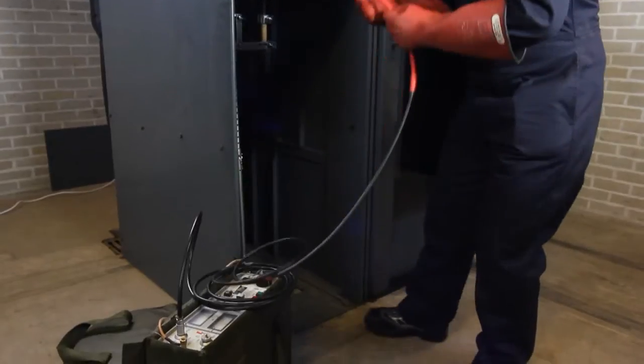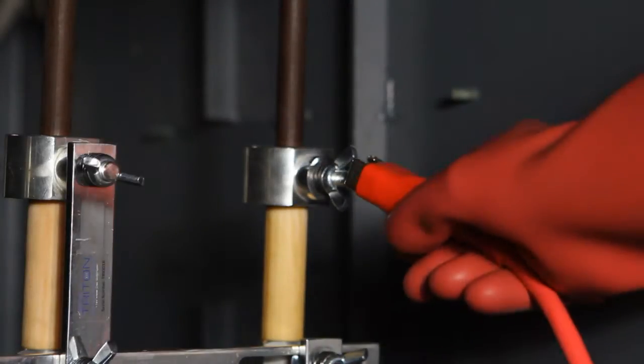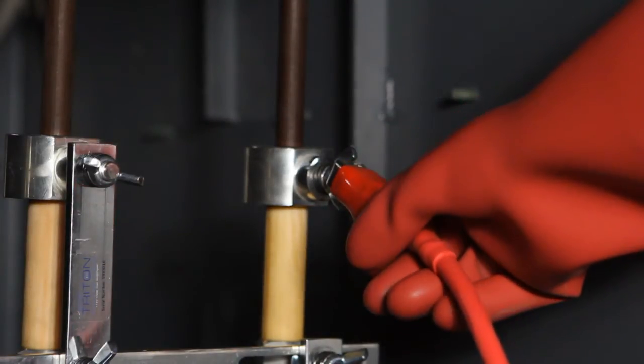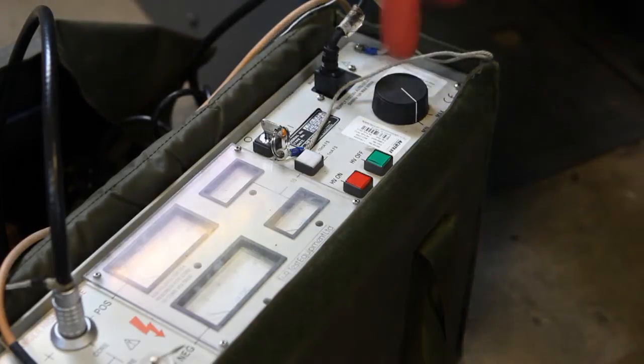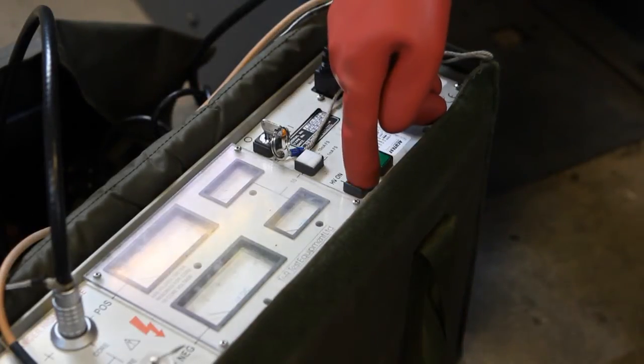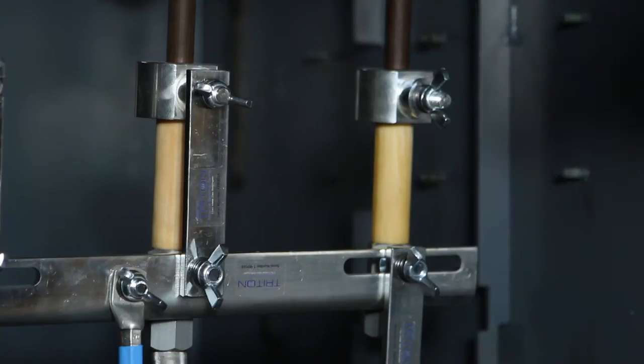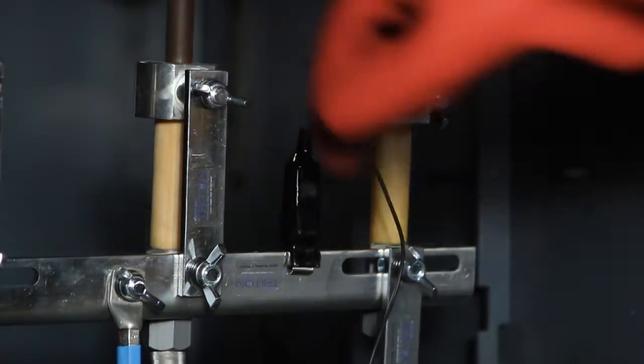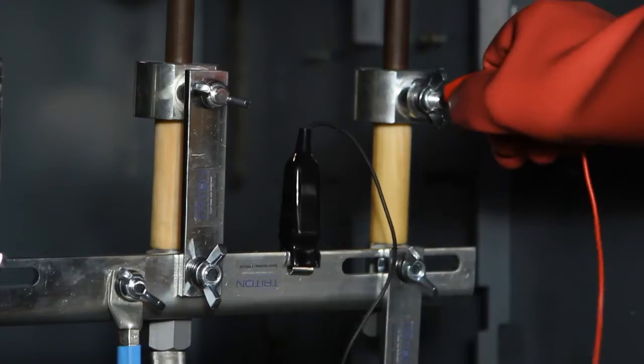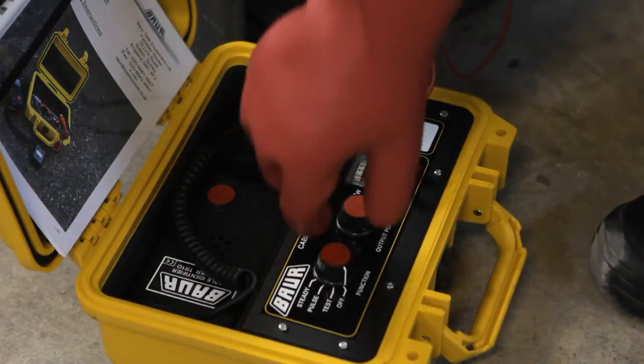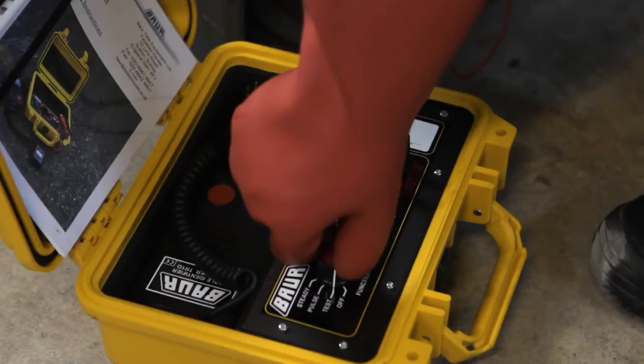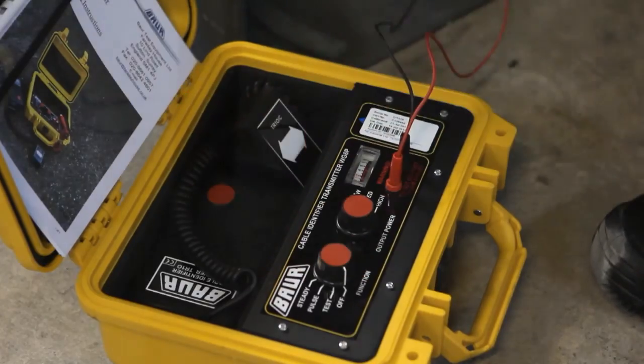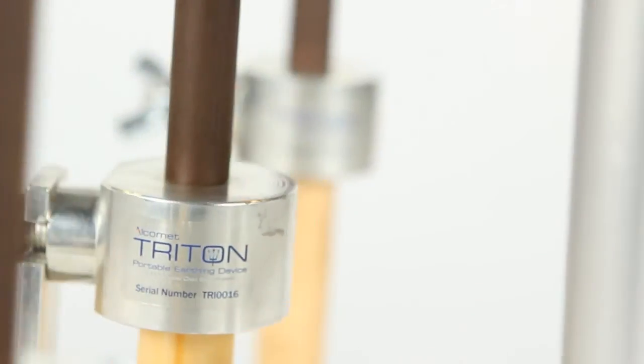Once the Triton is installed, it can quickly be converted into a rated testing device to facilitate fault location, pressure testing, cable identification or even primary commissioning tests. Testing is swiftly achieved by opening the test links and attaching your preferred test equipment. This saves time and effort, compared with traditionally installing and removing circuit breakers to facilitate the installation of test plugs.